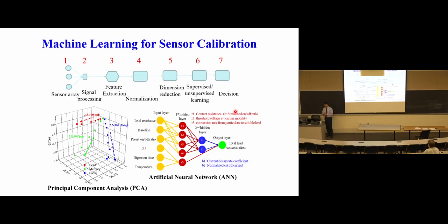So one of the directions we are trying to pursue is first to reduce the manufacturing variability to start with. Then you can also use more enhanced calibration approaches to come up with a better prediction. So we're leveraging machine learning models that can potentially take into account the history of the manufacturing process for each individual device, typically batch process, so that you can better predict the concentration of the analyte based on your individual device and also their sensor responses.